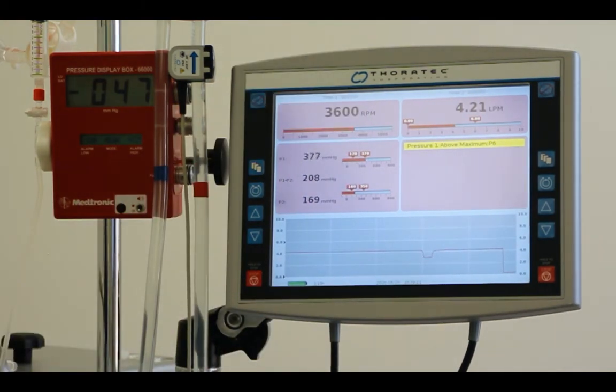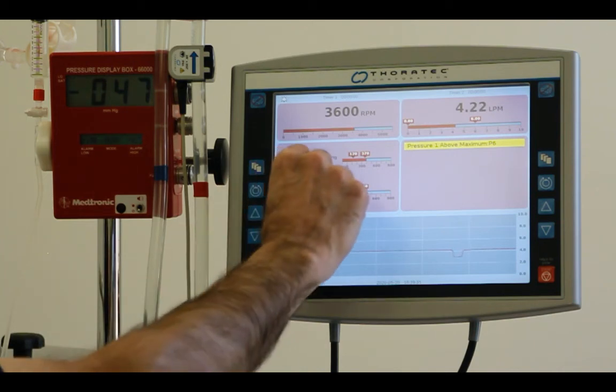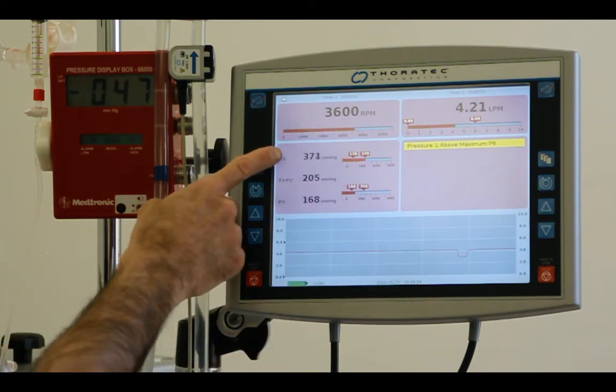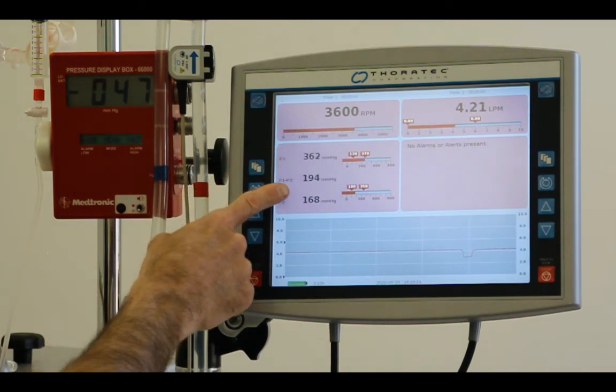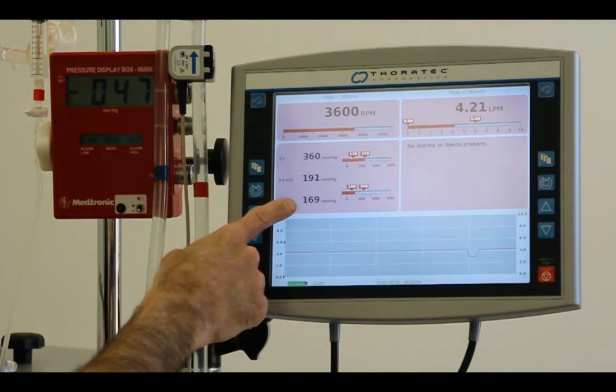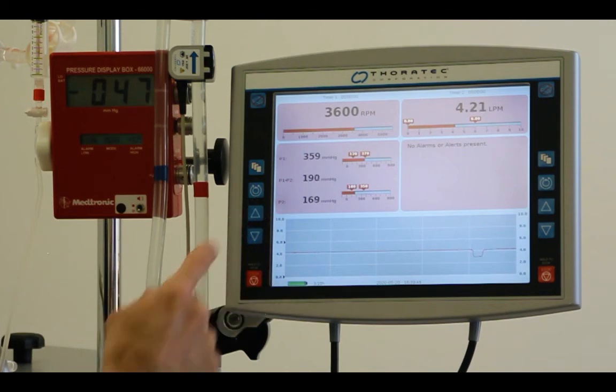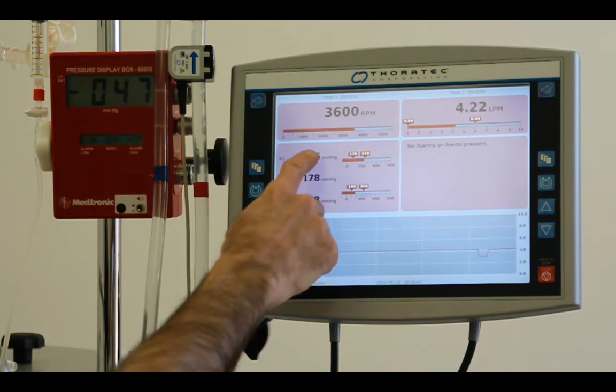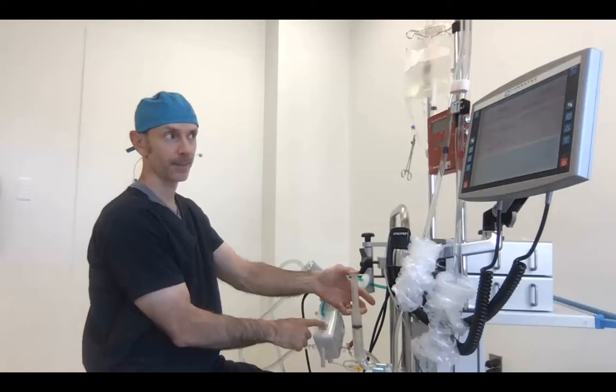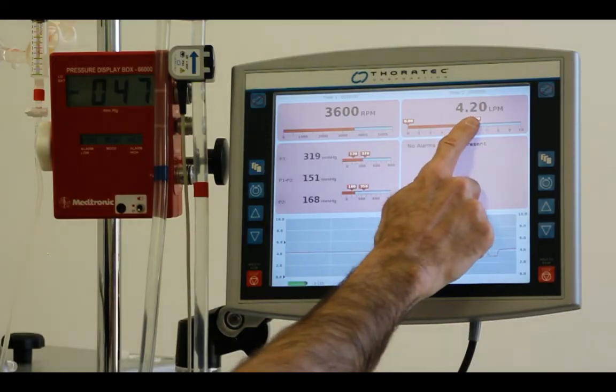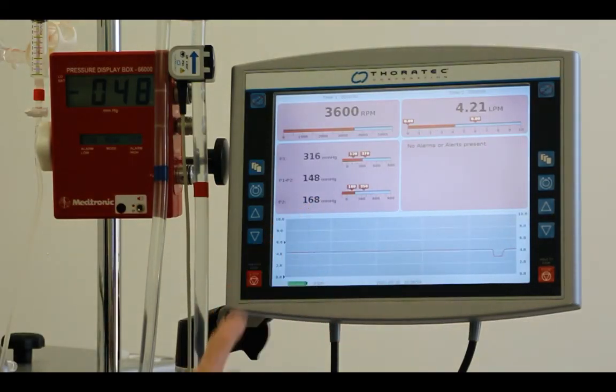Difference is, it doesn't happen this fast. It probably happens over many, many hours, days maybe even, before you get this kind of a difference of 200 millimeters of mercury, when normally it's 25. So the rising delta P plays out as an increasing pre-membrane, but generally until the end moment, it's an unchanged post-membrane. The resistance has to be so bad in here that it changes your flow before it affects that number there.